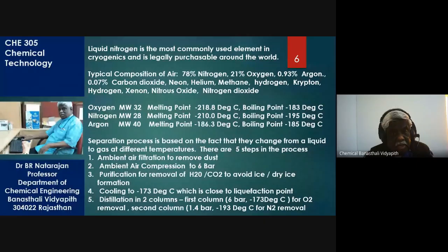Remember, for oxygen and nitrogen, if I have to use melting point as the property difference for exploitation, I have to achieve more excursion in lower temperature. I have to go to minus 210, minus 218 to separate oxygen and nitrogen, whereas I have to reach only minus 183 and minus 195. Remember, minus 183, minus 195 is relatively warmer as compared to minus 218 and minus 210. So if I have to go lower and lower, the cost goes higher and higher, right? So, as a thumb rule, we avoid excursion below atmospheric temperature and pressure, but wherever possible, we try to be on the better side. Okay, so exploitation of boiling point is going to be the main criterion for separating the mixture of air into oxygen, nitrogen, and argon.